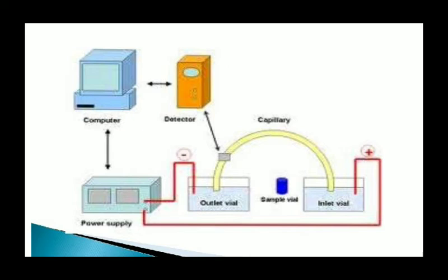You can see there is a capillary, and a compartment where injection and detection can take place. Ideally, any capillary you are using should be chemically and physically resistant, it should not absorb solutes, it should be transparent to UV visible radiation with a high thermal conductivity, and it should have a low cost. That type of capillaries we can use.